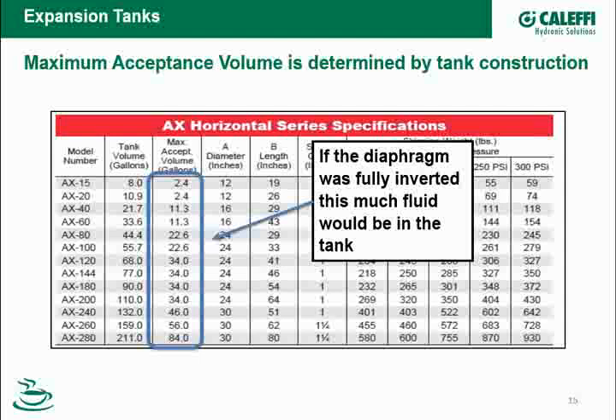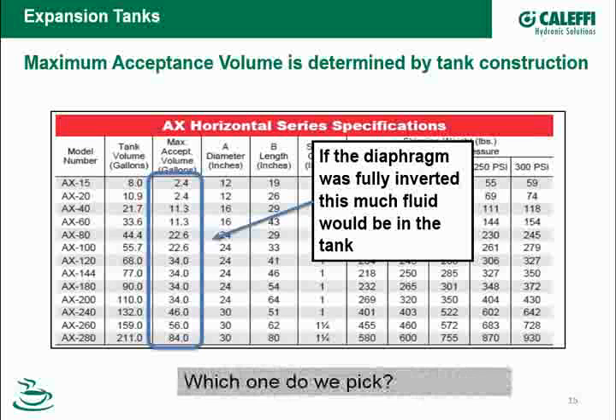And from the aspect of system design, since I don't want that diaphragm to stretch, when I select the tank I have to make sure that it will accept that volume. So for instance, I look at this AX20, its acceptance volume is 2.4 gallons. I have 2.75, so I may have to look at the AX40 as my tank choice. I want the max acceptance volume to always be more than the acceptance volume that's going into the system through expansion. Are there any questions?